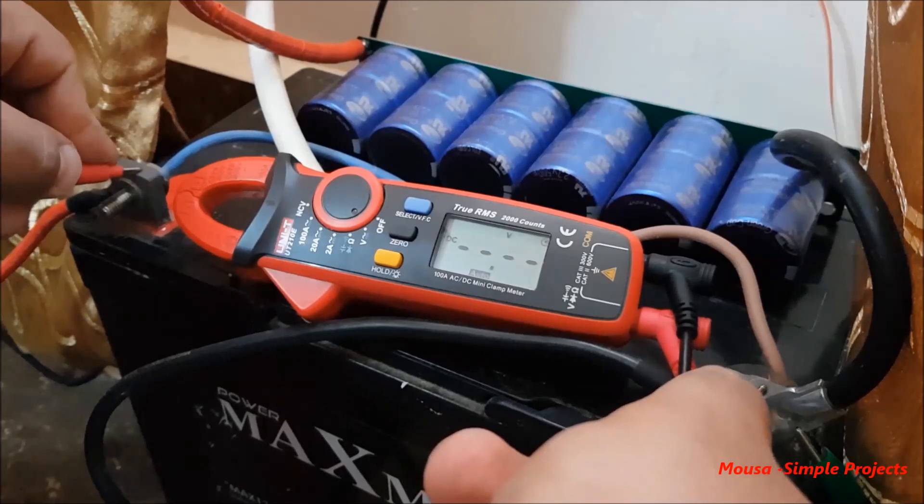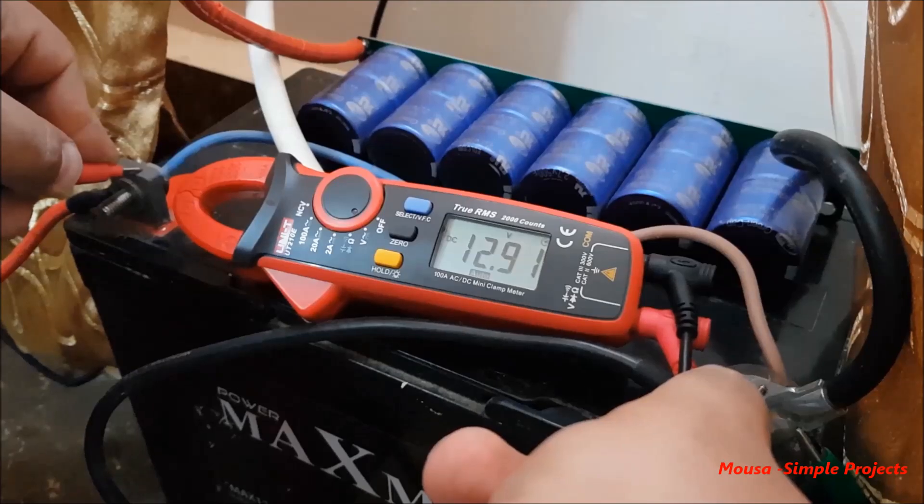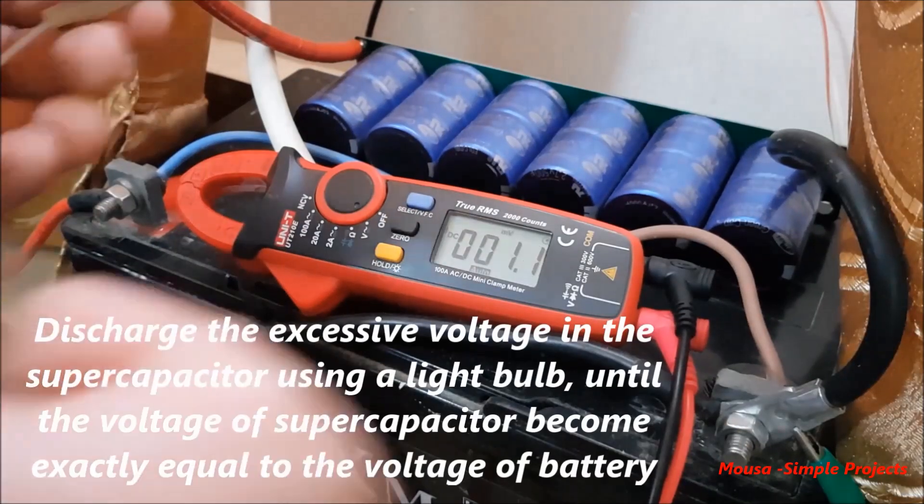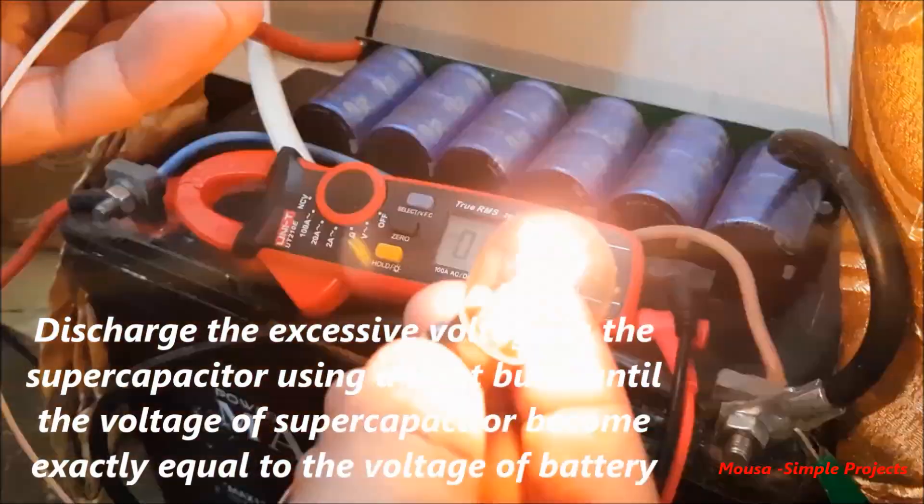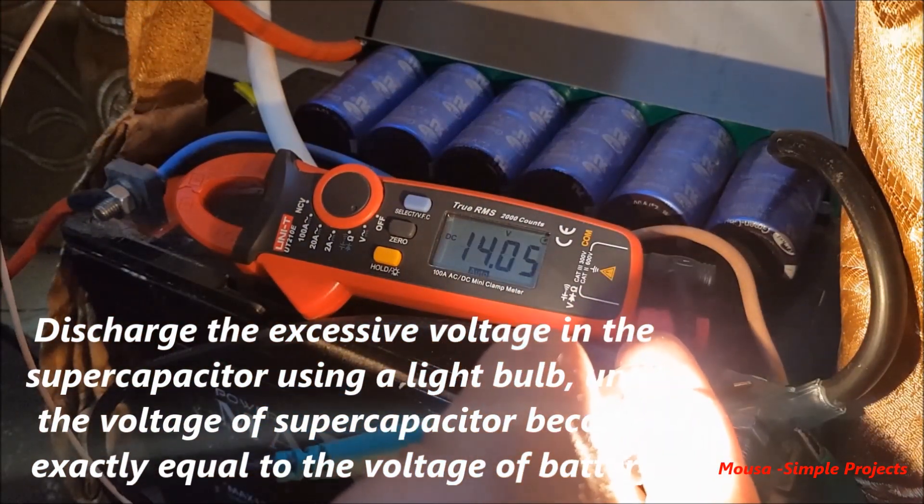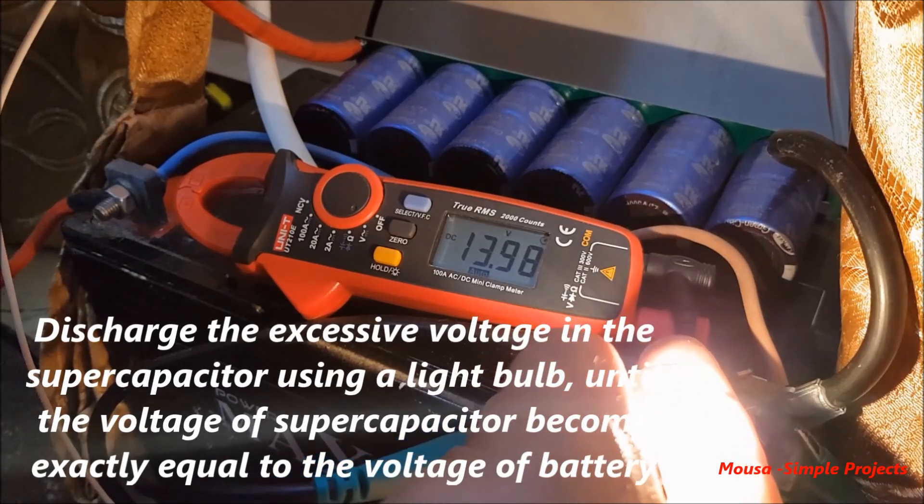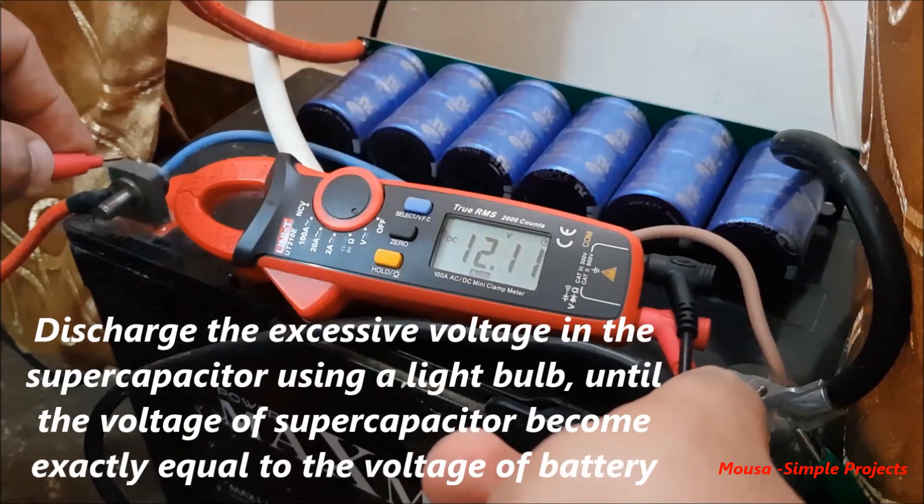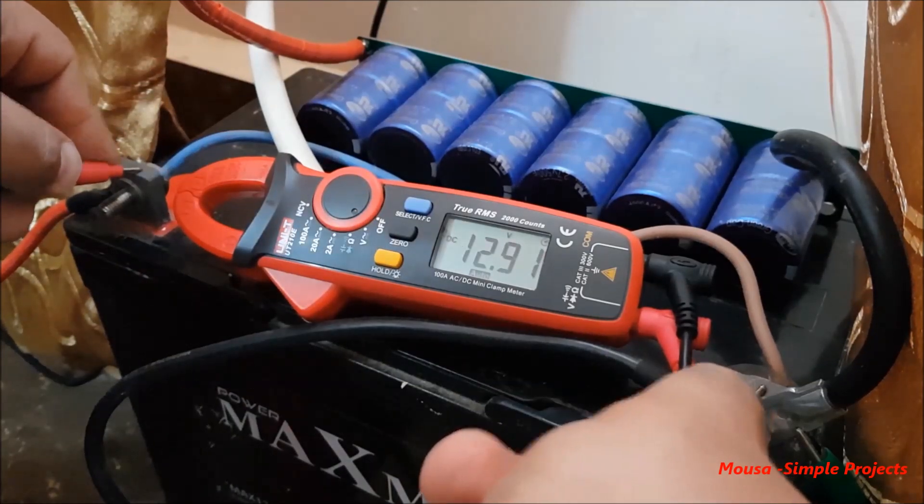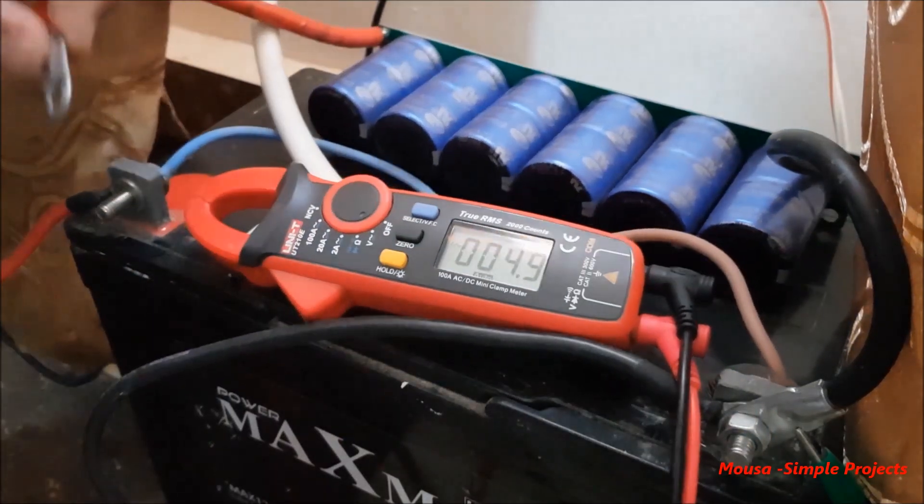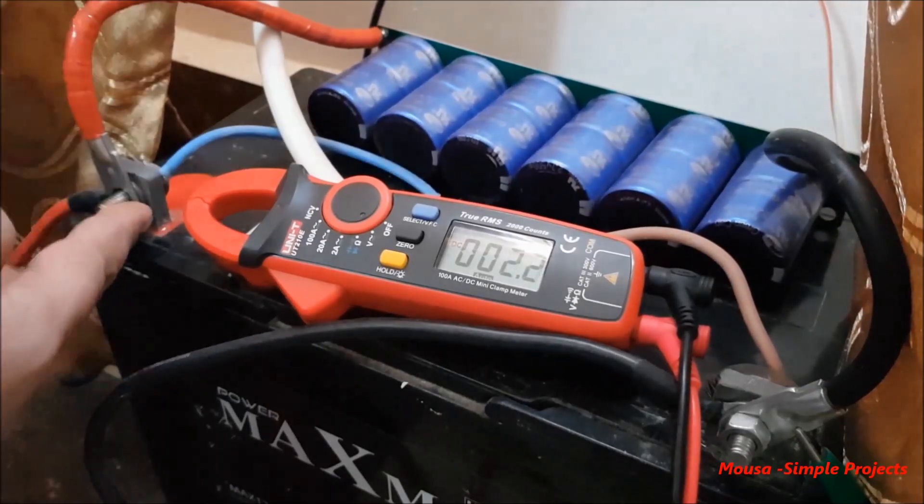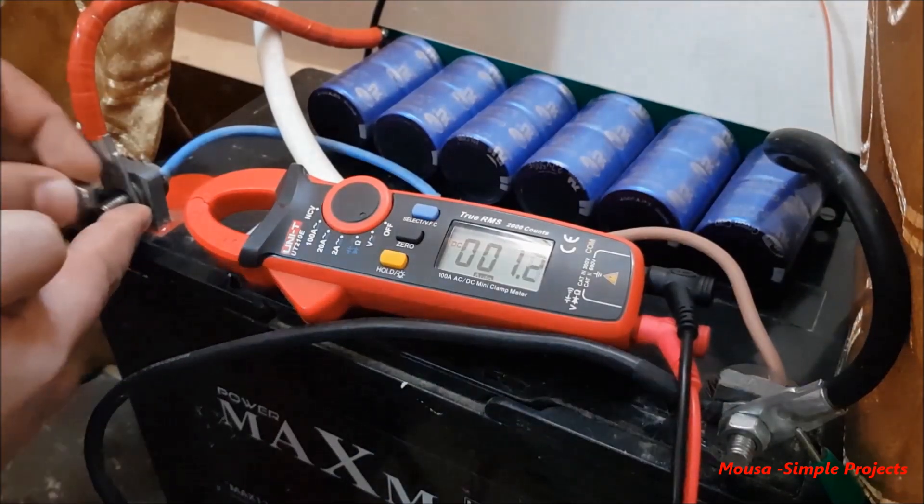Finally, if you want to connect this super capacitor bank to your battery of UPS or inverter, you should make sure that the voltage of the super capacitor bank is equal to the voltage of your battery. Otherwise, a huge amount of current will deliver from the battery to the super capacitor or from super capacitor to the battery, and that can be dangerous.